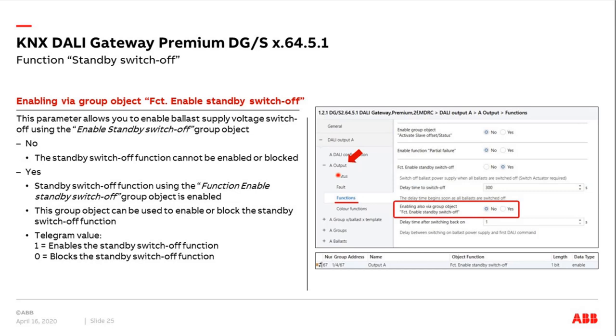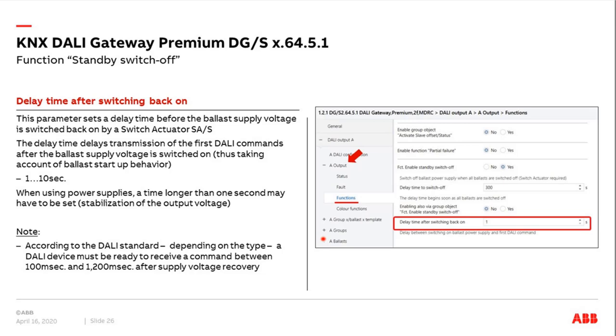You can also enable or block the standby switch-off function — for example, during the day, so only overnight the standby function is activated by the gateway. We can use a group object with value 0 to block it during the day and enable it in the evening. With group object 67, 'Function Standby Switch-Off Enable or Block': value 1 enables the function and value 0 blocks it. The delay time after switching back on defaults to one second; for power supplies, two or three seconds may be recommended.